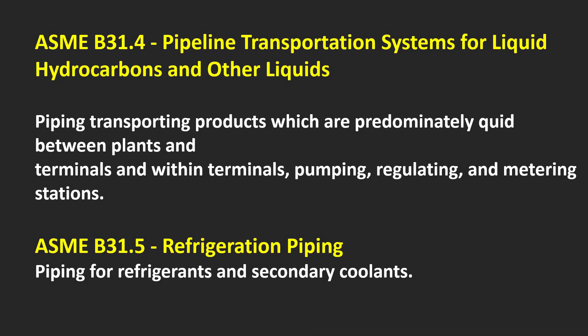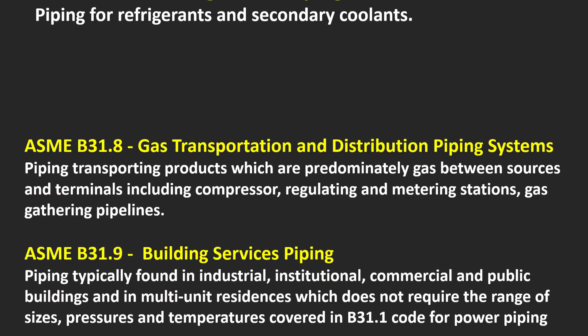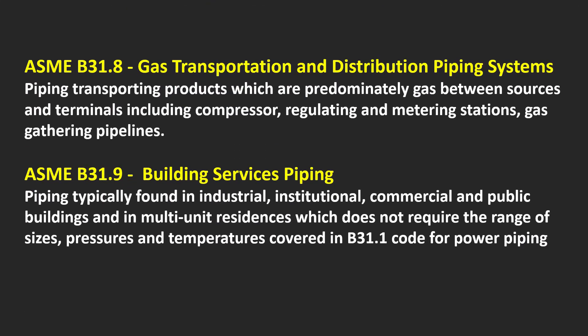ASME B31.4 covers pipeline transportation systems for liquid hydrocarbons and other liquids — piping transporting products predominantly between plants and terminals and within terminals, pumping, regulating, and metering stations. ASME B31.5 covers refrigeration piping for refrigerants and secondary coolants. ASME B31.8 covers gas transportation and distribution piping systems — piping transporting products between sources and terminals including compressor stations, gas metering stations, and gas gathering pipelines.